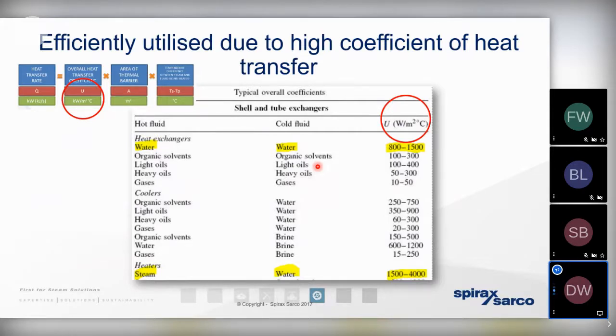Now, I suppose the downside of having a smaller heat transfer space, or a smaller A value, is we really need to be on top of moving that condensate away. Because we know that condensate, the byproduct of heat exchange, exists as a liquid. And that liquid condensate, as we know, has far, far less heat energy contained within it. So if that condensate is allowed to back up and flood the secondary side, flood the primary side, it means we're going to have a barrier to heat transfer. The heat transfer rate is going to slow down and slow down.